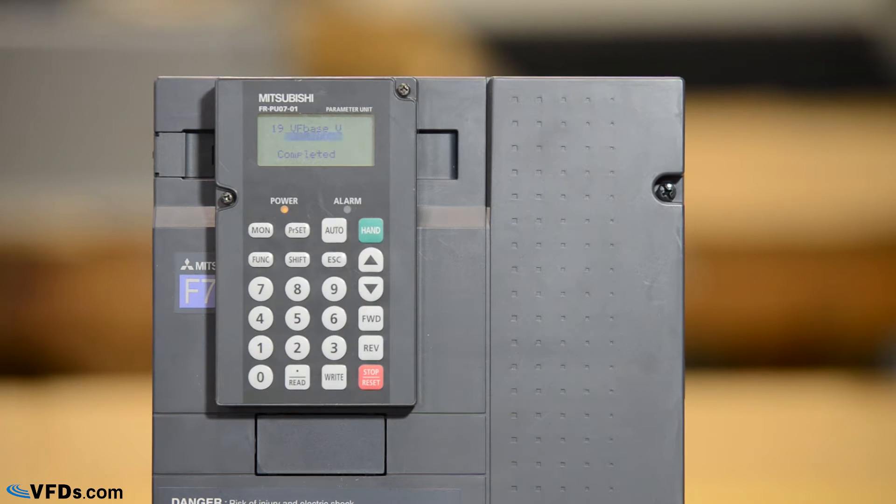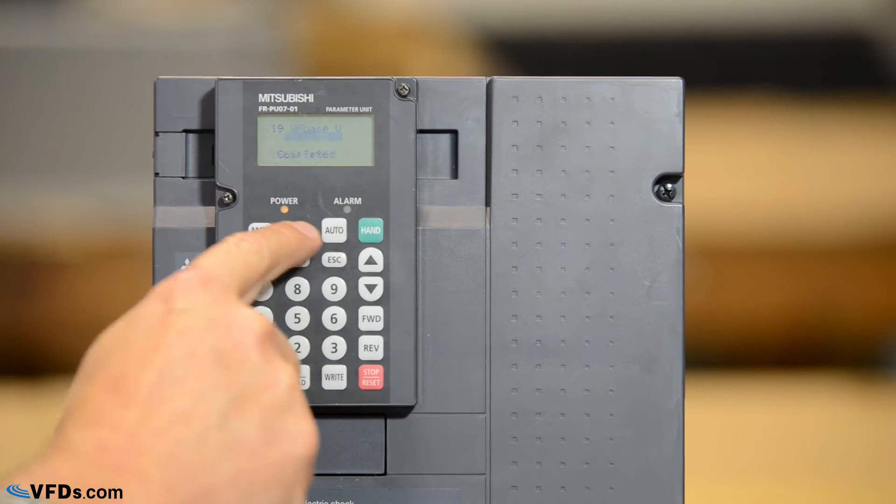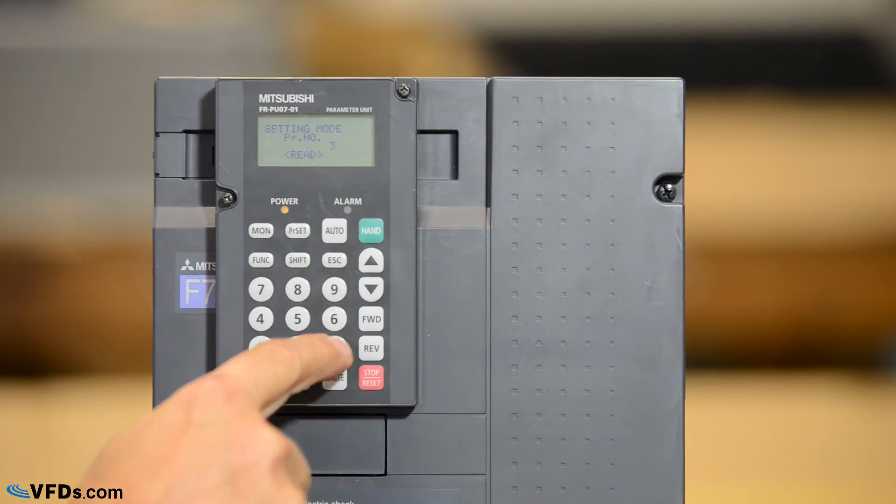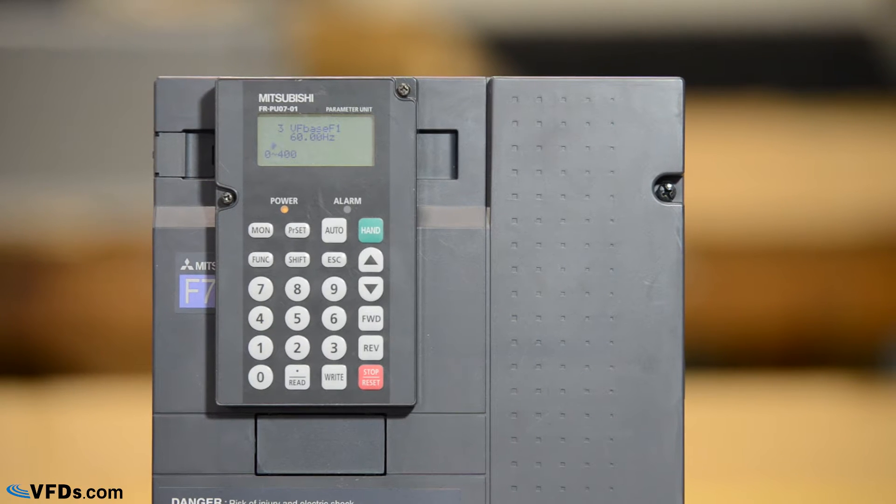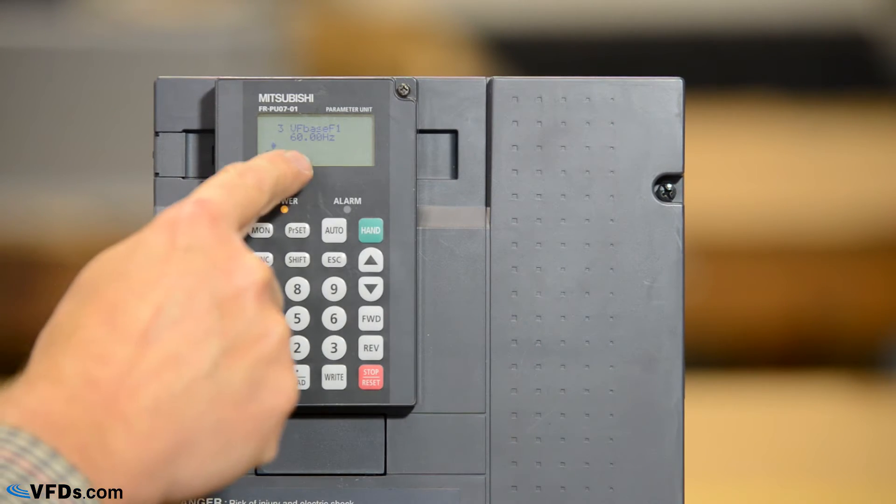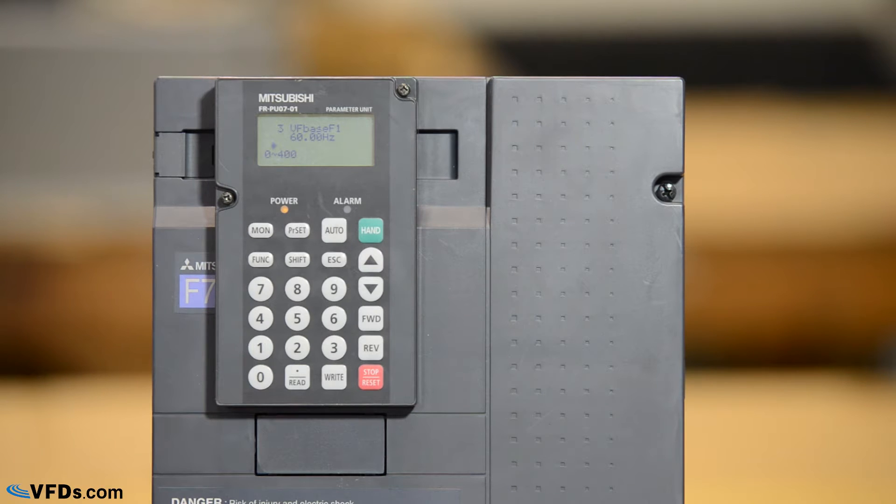The next thing I'll change is the frequency. So I push parameter set 3 and read and this is the motor rated frequency. In this case it says 60 hertz and that is the rating on the nameplate of my motor so I will leave that as it is.